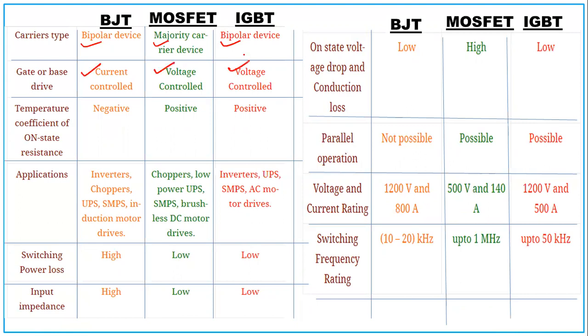BJT is a bipolar device, MOSFET is a majority carrier device, and IGBT is also a bipolar device. Importantly, BJT is current-controlled, MOSFET is voltage-controlled, and IGBT is also voltage-controlled. The temperature coefficient of on-state resistance is negative for BJT and positive for MOSFET and IGBT. Applications include inverters, choppers, UPS, and DC motor drives. Specific ratings: BJT 1200 V / 800 A, MOSFET 500 V / 140 A, IGBT 1200 V / 500 A. Switching losses are high for BJT, low for MOSFET, and very low for IGBT.